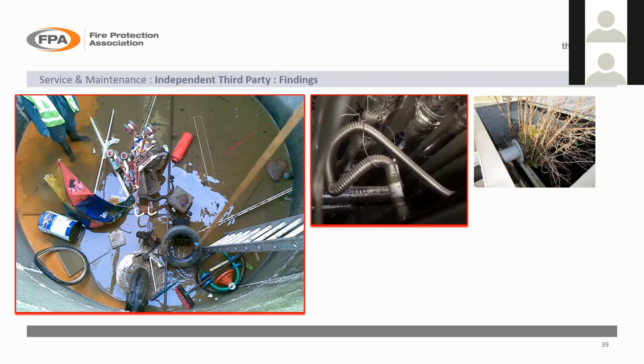Two pictures to go. This is the kind of thing that we find on an inspection. That's a flexible arm pipe to a sprinkler head. You can see there that somebody's kind of, well, first of all, there are manufacturers' recommended specifications on how it should be installed. That doesn't meet any of them because it's not been installed correctly. But equally, it's been tied up. It could have been done by a sprinkler contractor, maybe, or it could have been done by somebody else. Whoever did it, it's an unacceptable situation.